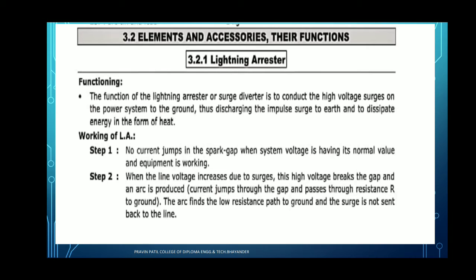First step, no current jumps in the spark gap. This is for the multiple gap, spark gap or horn gap lightning arrestor, where a gap exists within the lightning arrestor. No current jumps in the spark gap when the system voltage is at its normal value and the equipment is working. Next, when the line voltage increases due to a surge, this high voltage breaks the gap and an arc is produced. The current jumps through the gap and passes through the resistance to the ground. The arc follows the low resistance path to the ground and the surge is not sent back to the main line.